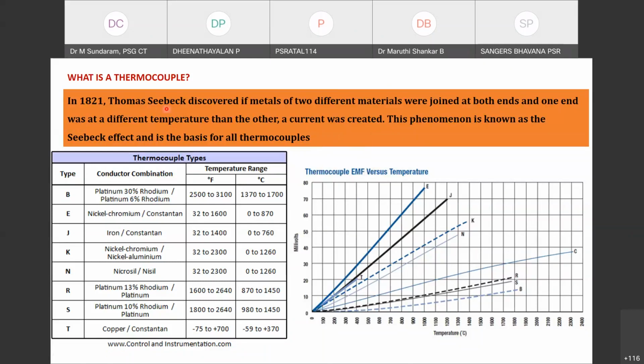But thermocouples have not stopped at that stage. Thermocouples keep getting upgraded. How? Because of metallurgical technology. See, thermocouples are classified as B type, E type, J type, K type, N type, R type, like this. Different types, with different material compositions: platinum, rhodium, nickel, chromium alloy, iron and constantan, nickel chromium alloy, and nickel aluminum alloy. Nicrosil is another alloy. Platinum 13% with rhodium and platinum.